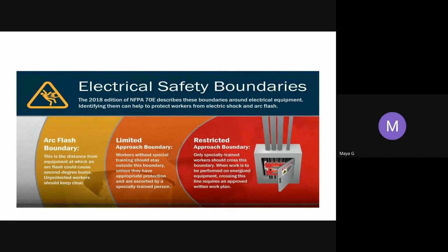We can see in this diagram the exposed conductor, and the red zone shows the restricted approach boundary. Only specially trained workers can cross this boundary when performing maintenance on the energized equipment. The orange line is the limited approach boundary, where workers without special training should stay outside unless they have appropriate protection and are escorted by a specially trained person. And the final boundary, the yellow one, is the arc flash boundary. This is the distance from the equipment at which an arc could cause second-degree burns. Unprotected workers should keep clear of these boundaries.